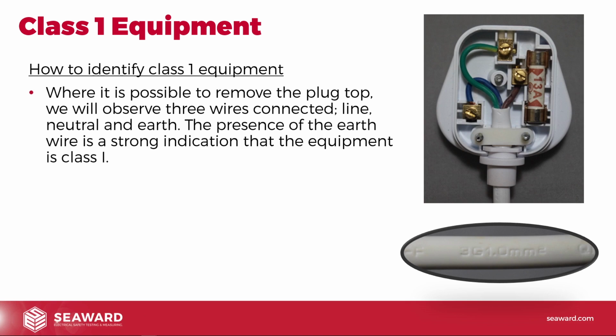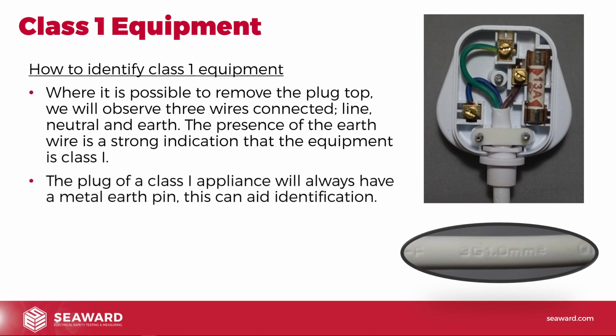It's not 100%. Sometimes Class 2 equipment does have an earth for functional screening purposes. Maybe anti-static dissipation is quite common on vacuum cleaners and things, where they have an earth there to stop static build-up, and that's not there for fault protection. But generally, in most cases, if you can take the plug top off and you look in there and see there's an earth wire in there, 99 times out of 100, that means that's going to be Class 1 equipment. The presence of the earth wire is a strong indication that it's Class 1 equipment, as I said.